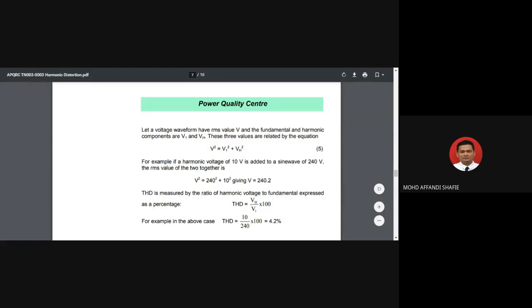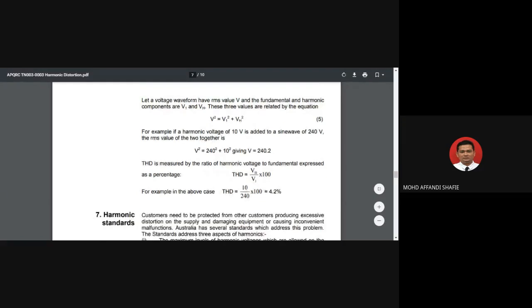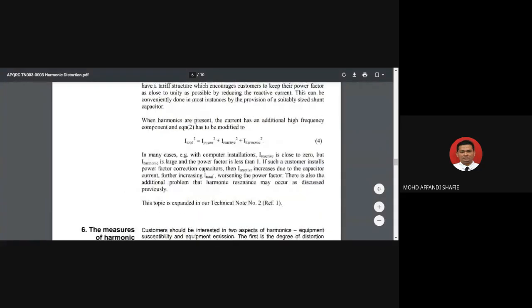So for example, if a harmonic voltage of 10 volt is added to a sine wave of 240 volt, the RMS value of the two together is 240 volt for the fundamental lah. So V squared is 240 squared plus 10 squared, the harmonic, giving 240.2. So THD is measured by the ratio of harmonic voltage to the fundamental, expressed as a percentage. So THD is harmonic 10 over fundamental 240. So for example, in the above case, our total harmonic distortion is 4.2%. So this is a simple calculation for how we calculate the harmonic distortion.